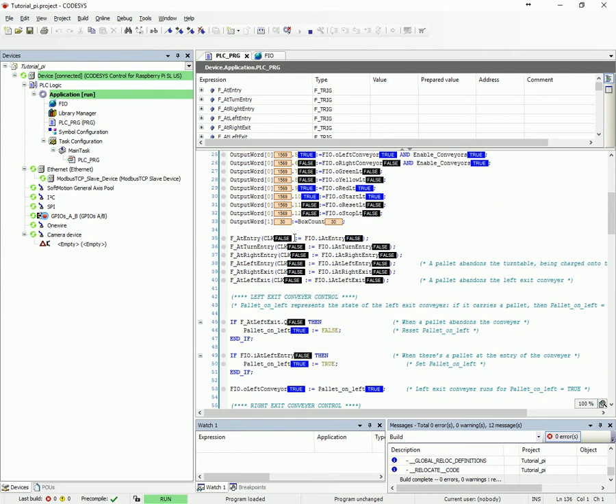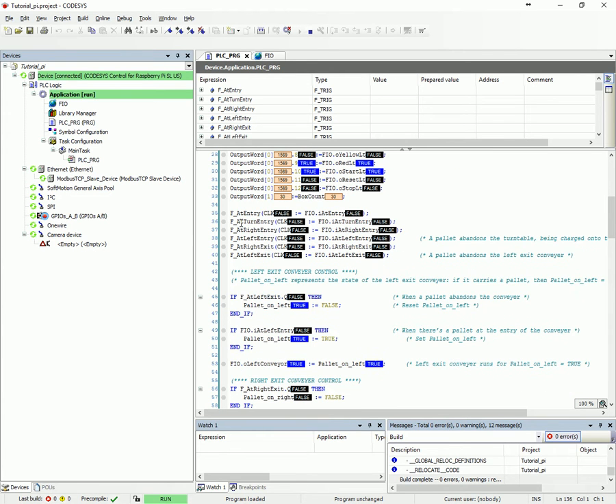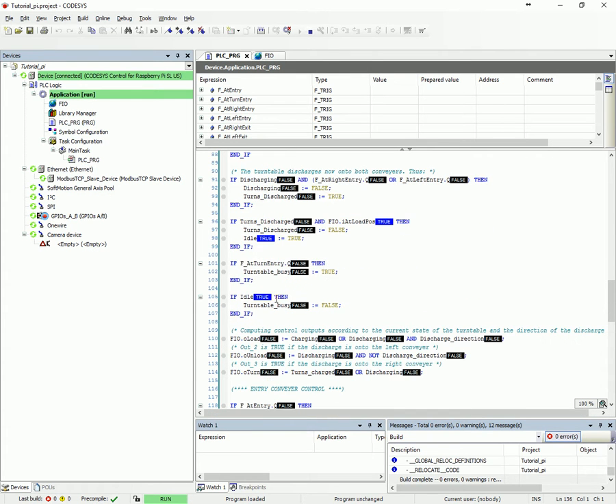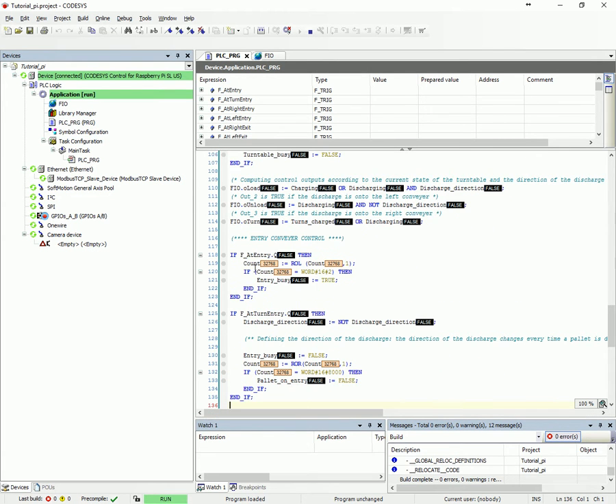Here we have some falling edge triggers. So when we get an input on the falling edge of that input — which means when it turns back off — that's when you'll see this falling edge trigger, like at that entry. Down here you'll see that it's only on for one scan, and here it executes this code.